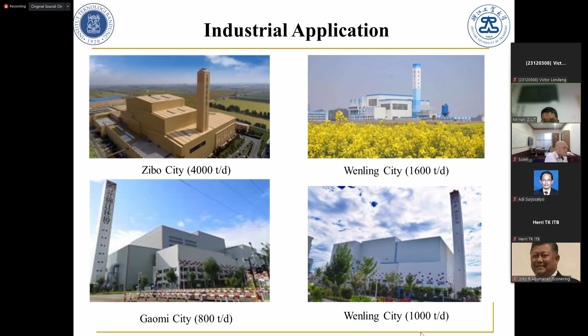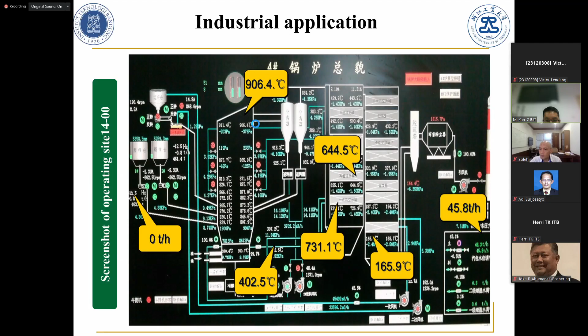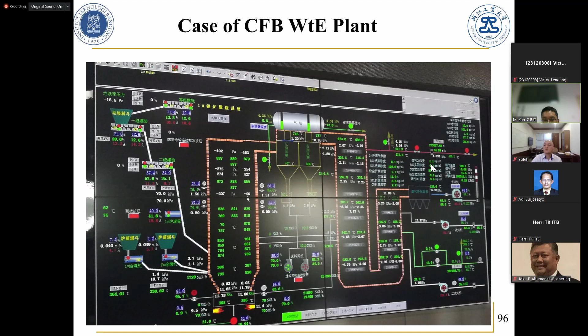So this is the DCS of the CFB. The inside is under vacuum, so the flue gas will not go out. So the temperature can reach 900. The output is 906 centigrade. And this is another CFB. The pressure inside the furnace is negative 254, so the vacuum is higher than the grate furnace. The grate furnace is usually negative 30 or 40 Pa, but for CFB it is over negative 200. Of course, the emission is very low. CO is only 1.1 mg per cubic meter.